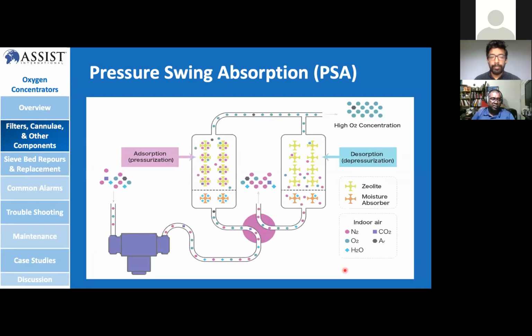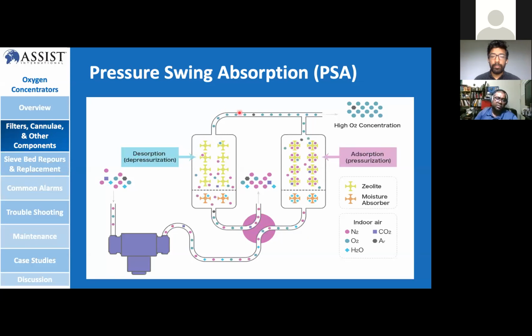You can see how it works. When the first one is absorbing, the other one will be releasing. At the same time, you can see the valve changing and releasing the nitrogen and all other gases out, and restarting, leaving the oxygen concentration through these two zeolites. So it will be switching the pressure for each tank to get the oxygen. All the switching is done by the valve. So that's how it works.